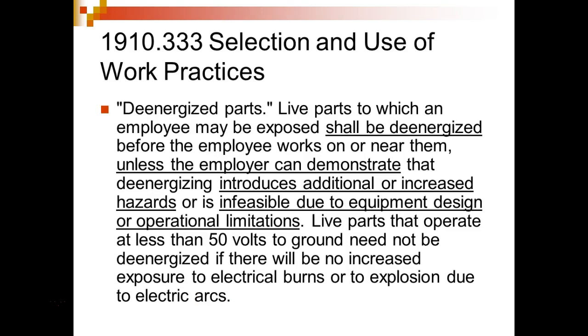De-energized parts. Live parts to which an employee may be exposed shall be de-energized before employees work on or near them, unless the employer can demonstrate that de-energizing introduces additional or increased hazards or is infeasible due to equipment design or operational limitations. Live parts that operate at less than 50 volts to ground need not be de-energized if there will be no increased exposure to electrical burns or to explosion due to electric arcs. So it doesn't say it's safe to work on 50 volts. It just says there can't be any other potentials in there, right?